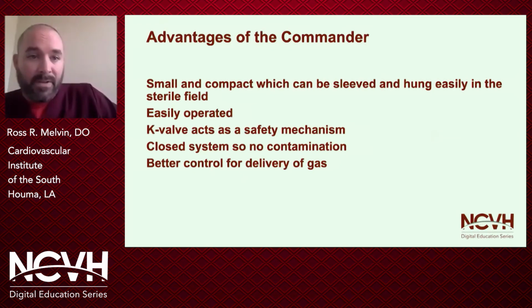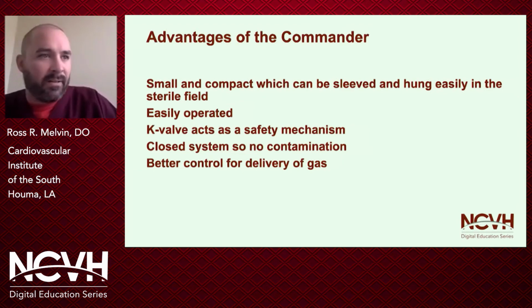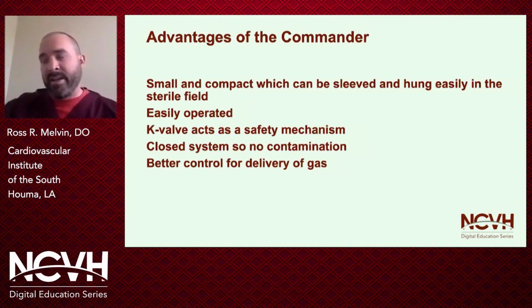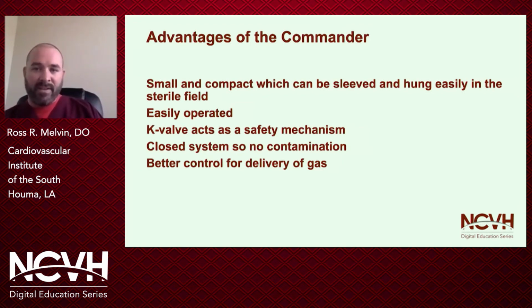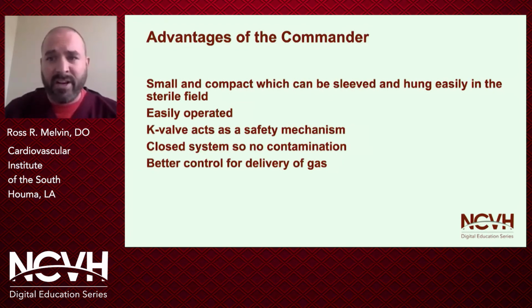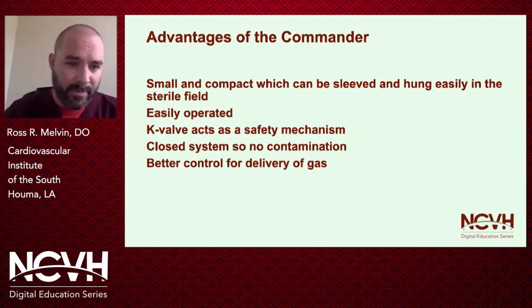So advantages of using the Commander: small, compact. As you saw, it was easily held in a sleeve. And you don't need the actual whole setup. You can just lay it on the table if you have a sleeve for that. We often do that in the lab here. Easy to operate. Once you've seen it done, it's like see one, do one, teach one. And like we talked about, that K valve acts as a safety mechanism, so you're not perforating any vessels by directly injecting into the patient from the device. So that's about that.